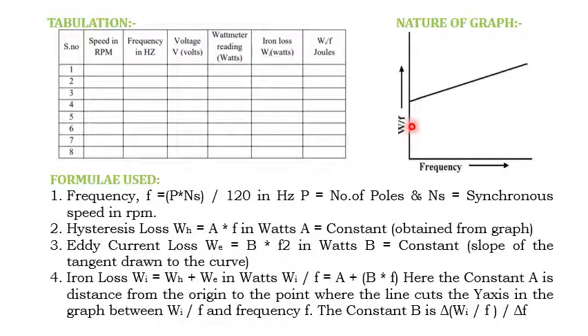From the origin to this point, this is the A value. You can obtain it from the graph. The frequency you know, since we conducted the test at different frequencies, so we calculate the hysteresis losses for the different frequencies. Then the eddy current loss can be calculated by We equals B into F, sorry, B into F square.